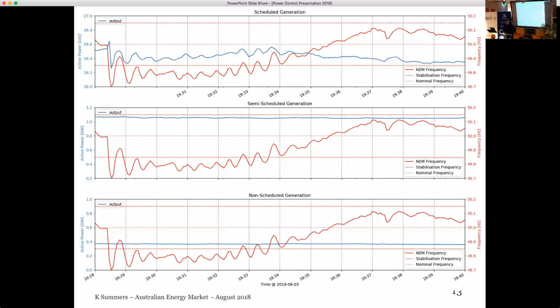They're good, but we need to fix that before they break themselves. Then we can integrate our batteries comfortably and know what we're dealing with. We'd know exactly how many cycles we'd have if we put a tight frequency band on things, and put a proper droop system in place so it would actually control. I would happily put droop on my wind farm if these guys were behaving themselves.